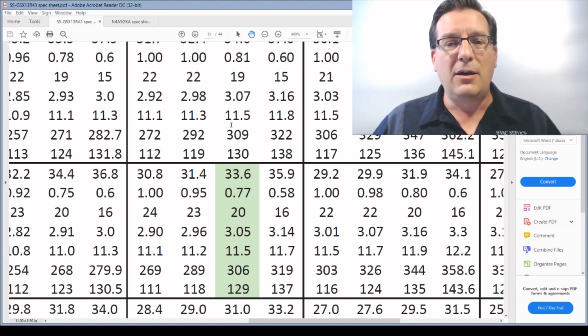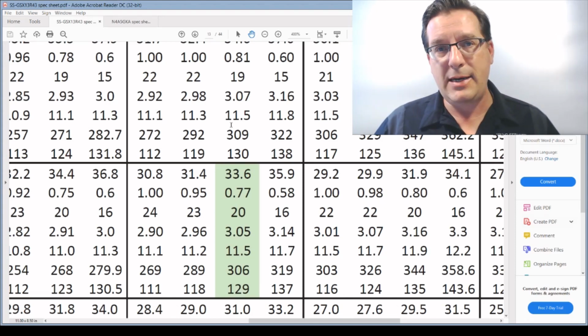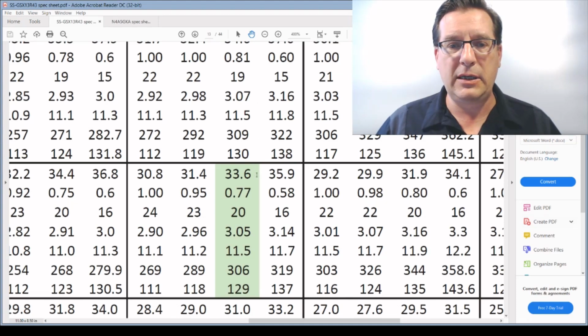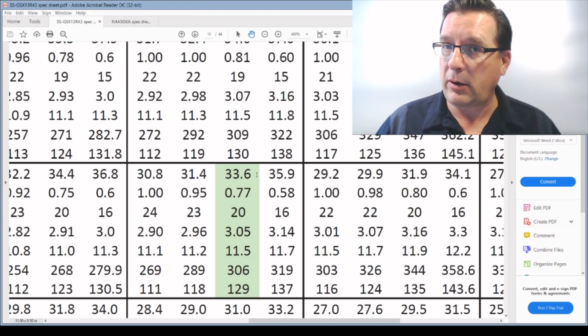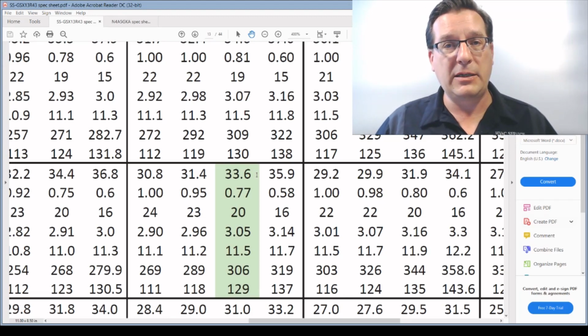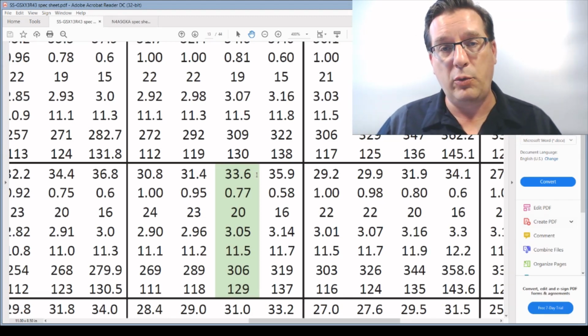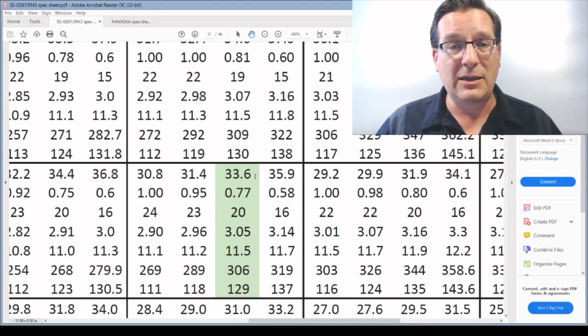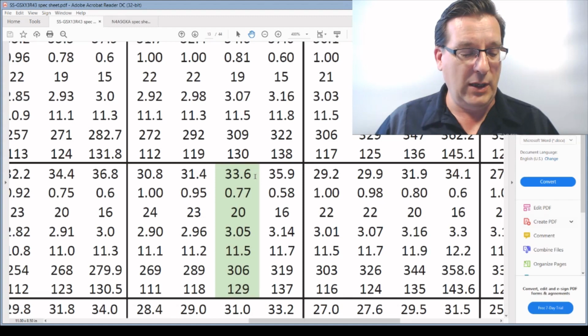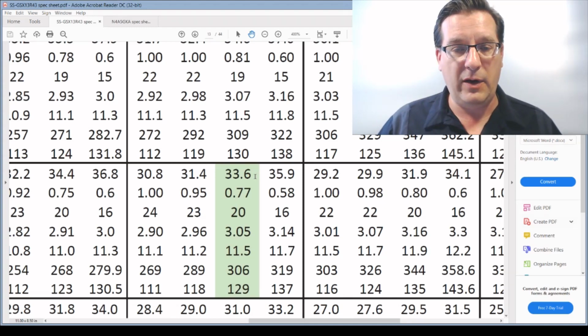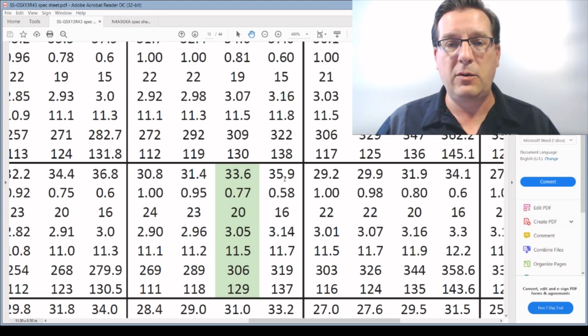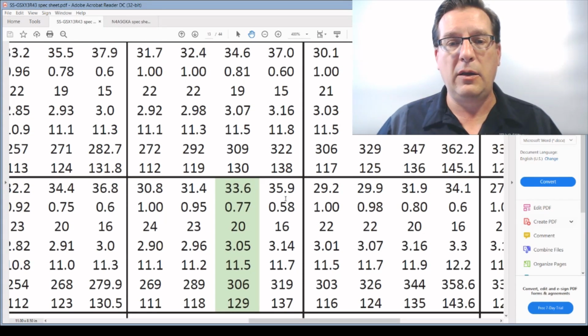Okay. So at design conditions for a nominal 3-ton AC, the total heat removal, as you can see, is 33,600 BTU per hour. Now you may notice that if this unit was specified as a 3-ton, 36,000 BTU per hour unit, 33.6 is something less than that. That is true. The way they rate these can vary from manufacturer to manufacturer. If you notice the next column up, when we get to a higher wet bulb value, we go from a 67 wet bulb up to, I believe that's a 71 up there. The total heat removed goes up to 35.9. It's about 36,000 BTU. So that's where that comes from.